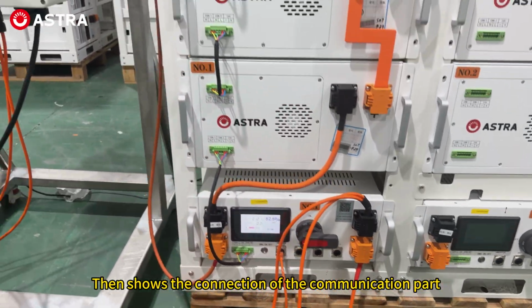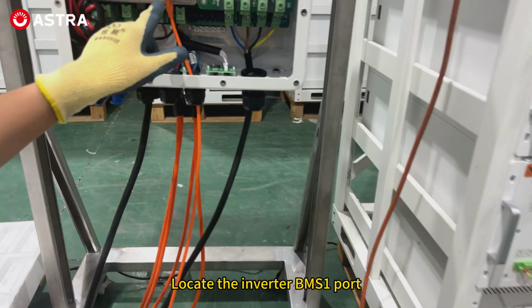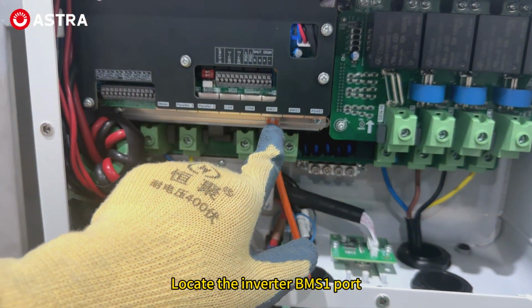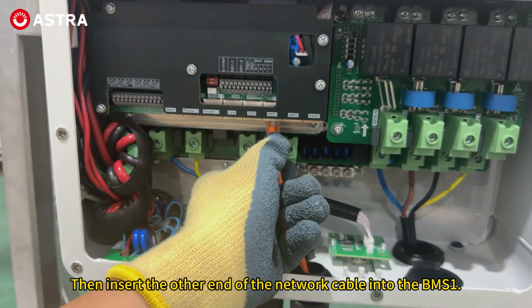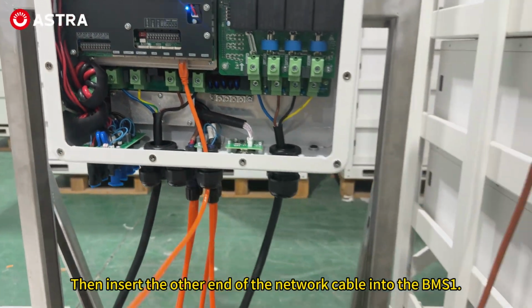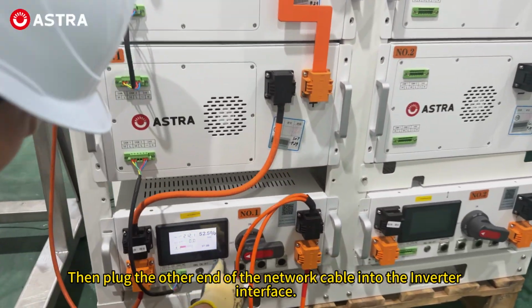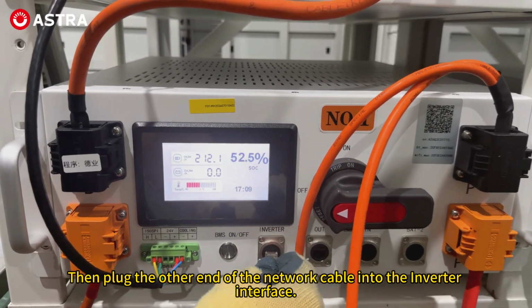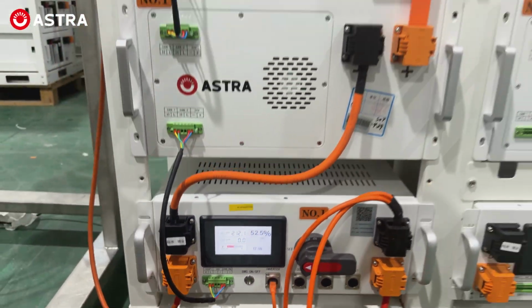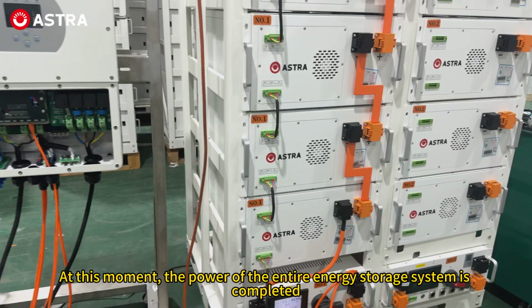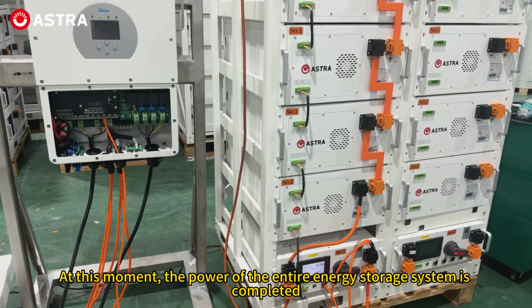Then I show the connection of the communication part. Locate the inverter BMS1 port. Then insert the other end of the network cable into the BMS1. Then plug the other end of the network cable into the inverter interface. At this moment, the power and communication connection of the entire energy storage system is completed.